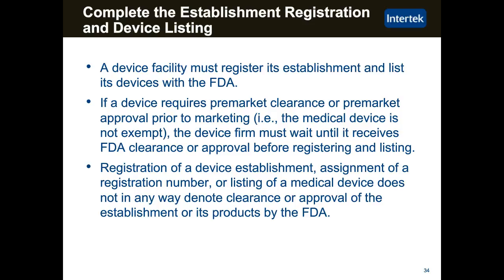In addition, if you have a registered device, it doesn't mean that you can automatically bring other devices to market. You need to verify whether or not that other device, or a new or subsequent device, requires a pre-market notification, either a 510K or a PMA or a de novo, before you bring that to market. There have been instances where people misunderstood the law and thought that once they were registered, they could bring as many products to market as they chose after they got that first 510K through, and that is not the case.